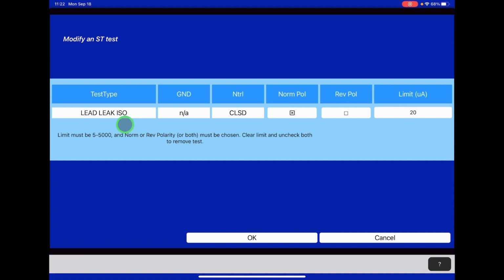And so you'll see in the service manual, it calls out for using a multimeter and making sure you're using a 120 k ohm resistor to do this test. Well, that's referring to a manual way to do the electrical safety test. But since we're using the safety sim, that resistance is built into the unit, and the unit itself will apply the mains voltage to the device, so you don't need to configure any external things like that 120 k ohm resistor. And of course, the limit here for this test is 20 microamps.